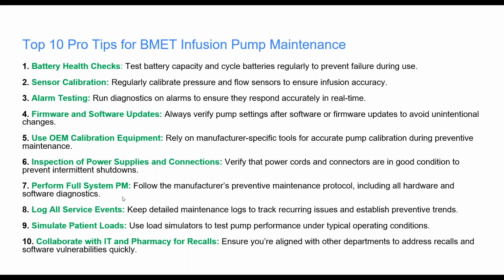Just as an assurance, because we know that sometimes things go out of the shop and then they fail. Make sure that you're up to date on your firmware and software. Use OEM calibration equipment. Now, I'm glad Robert mentioned this, the Baxter pumps. Baxter is not the only one that has a recommendation to use a scale, right? And deionized or distilled water, I believe it's deionized.